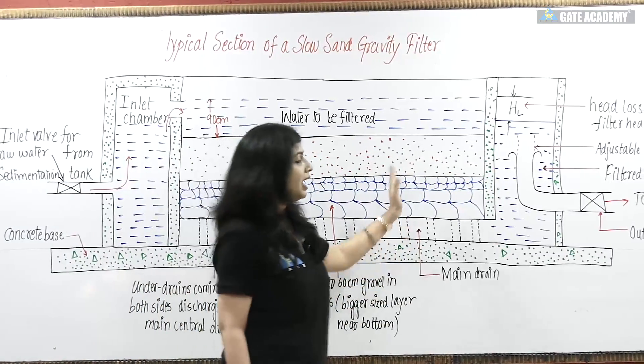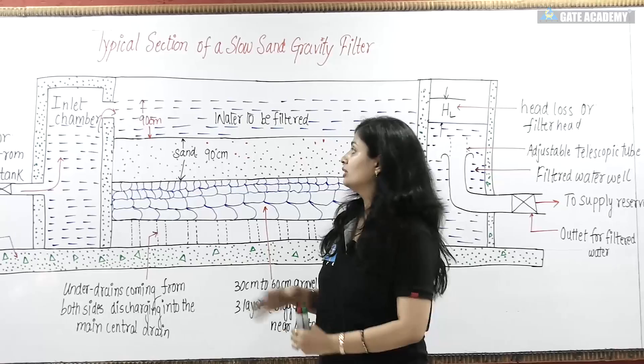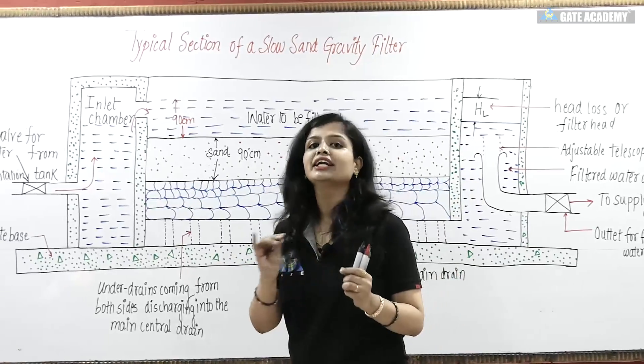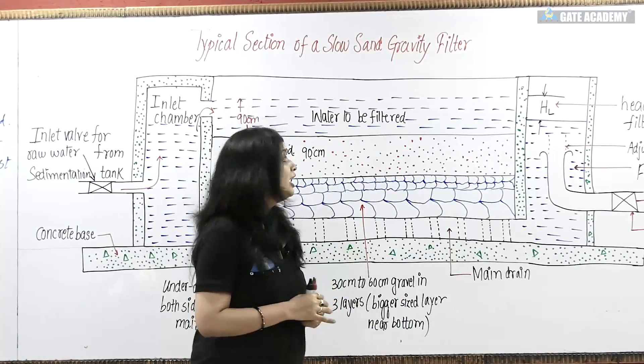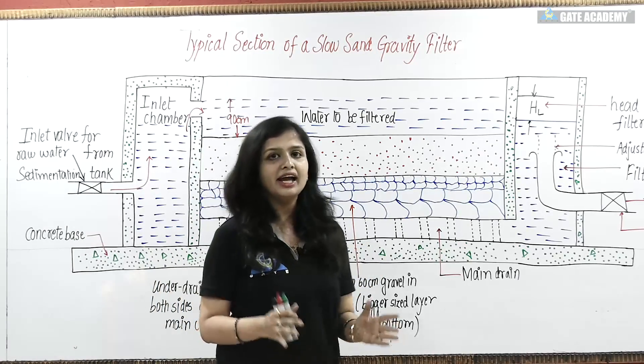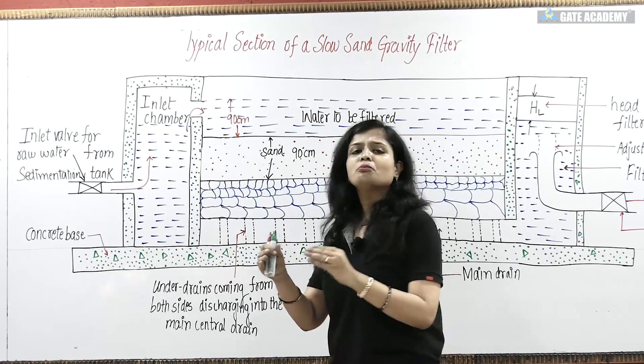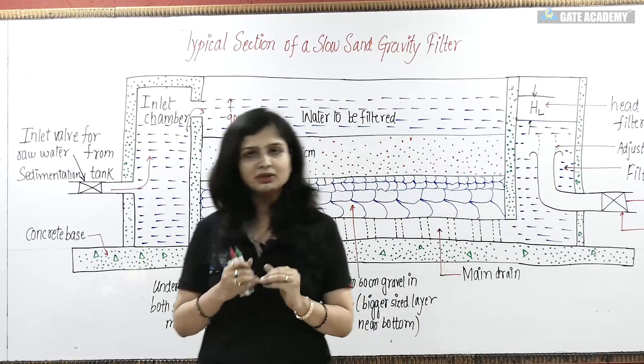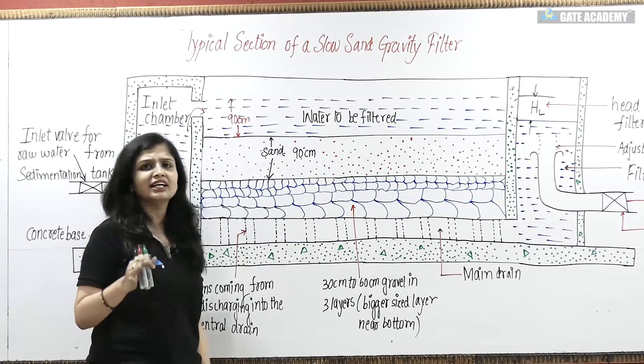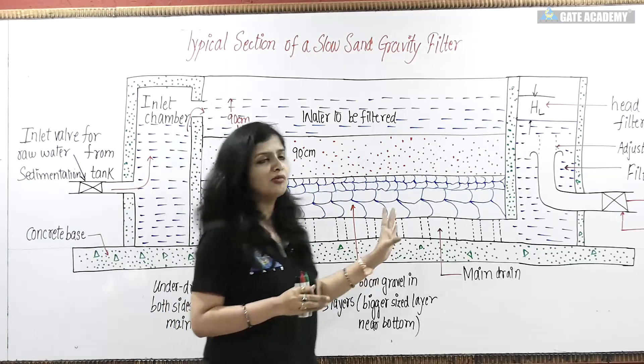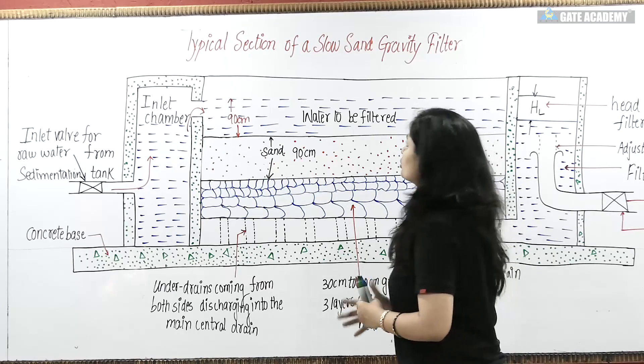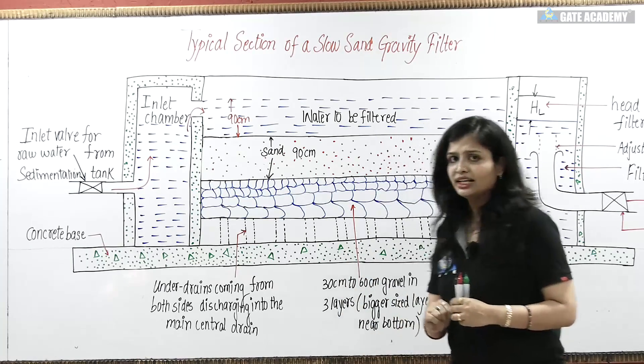After cleaning, how much water is required? Back washing is not applicable here. For cleaning of slow sand gravity filters, you use 0.2 to 0.6% of the total filtered water volume. Cleaning frequency generally depends on how much water you are filtering, but typically you have to clean every 1 to 3 months in slow sand gravity filters.